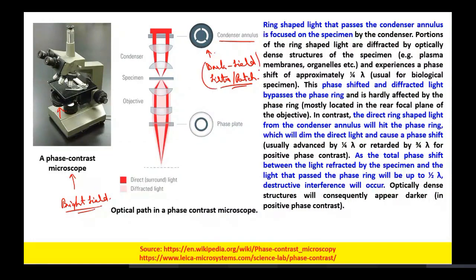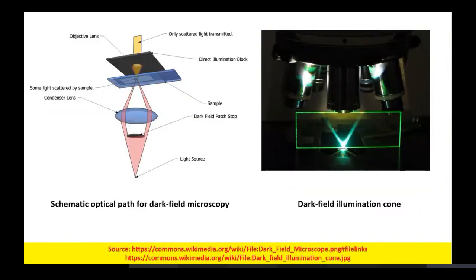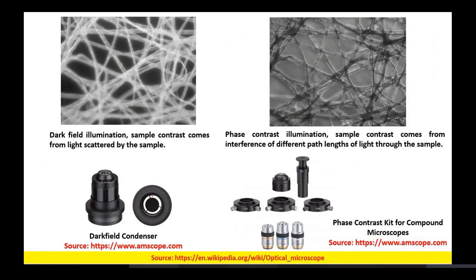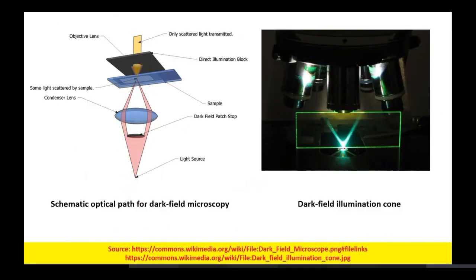Through this dark field filter and patch, the light from the annulus passes through. When it passes through the system and falls onto the slide, it forms a V-shaped light cone with no light in the center. This happens due to the dark field patch stop, which prevents light from passing through that central region, giving us a conical shaped light system.